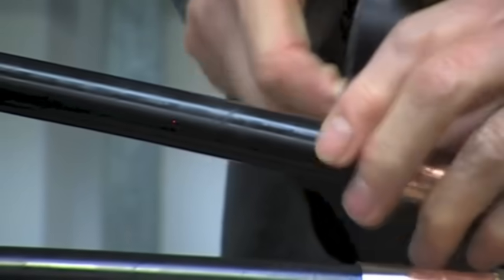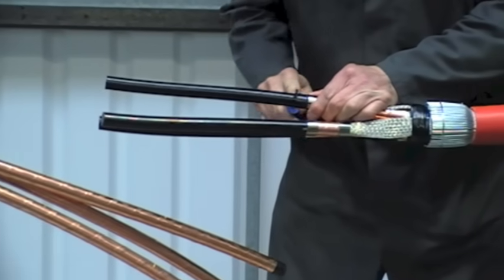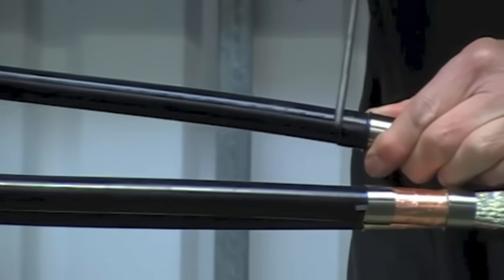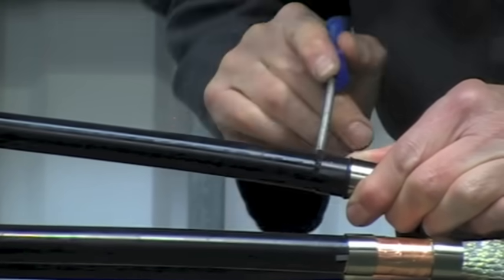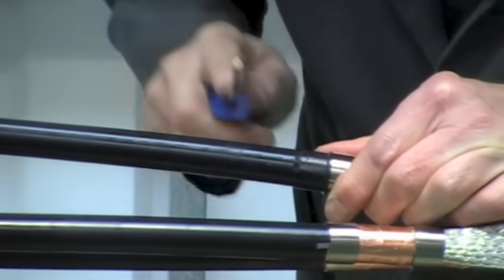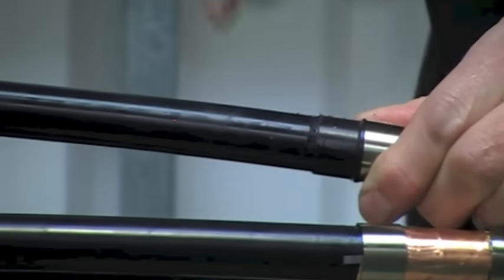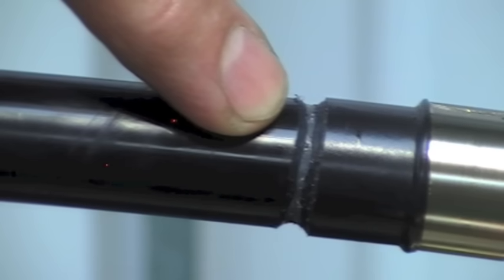The best method of removing the easy strip type semi-conductive screen is by using a round file or commonly known as a rat tail file. File around the core as shown until you see the white primary insulation beneath. Do not use a sharp knife or a Stanley knife to do this.